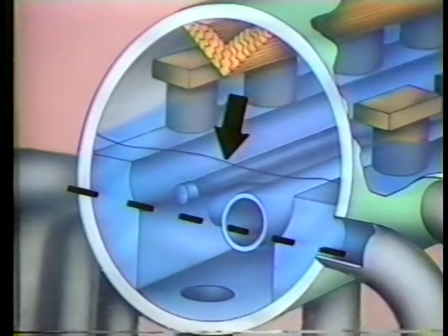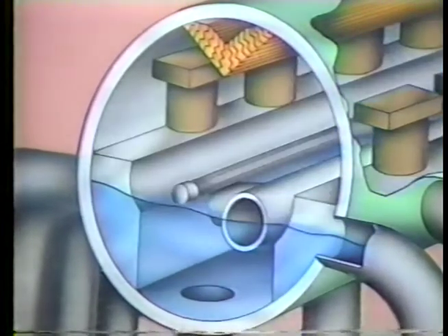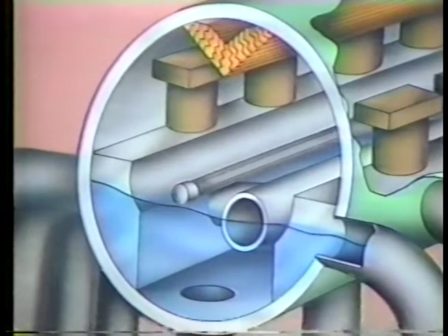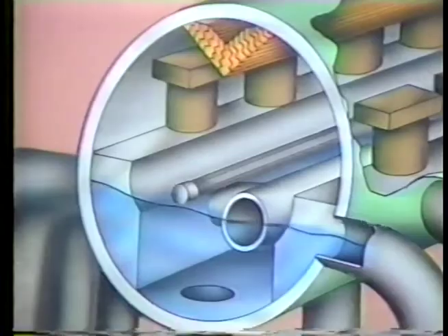This higher level is required to allow for the decrease in level which occurs when the boiler water circulating pumps are started up. By contrast, on natural circulation drum type boilers, it's not uncommon for the firing level in the drum to be lower than the normal operating level. A lower level is necessary in this case to allow for the expansion which takes place when the water in the water wall tubes begins to boil.